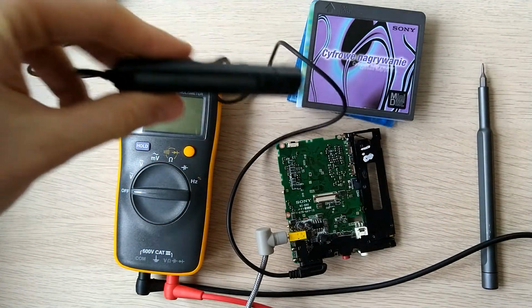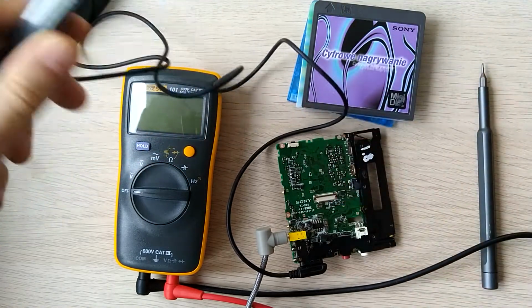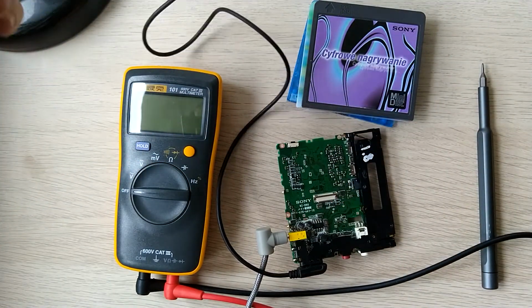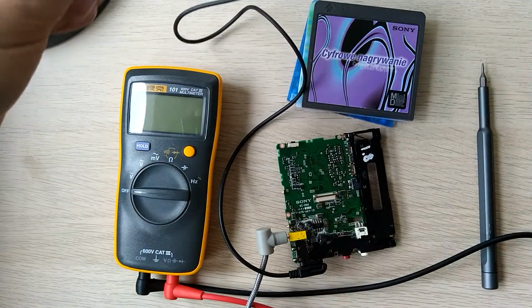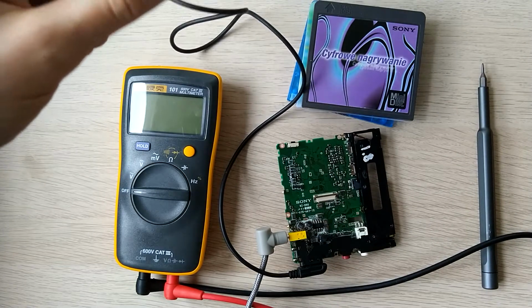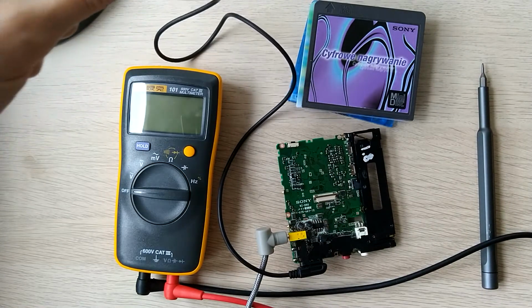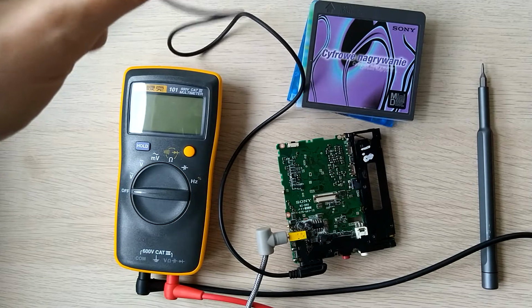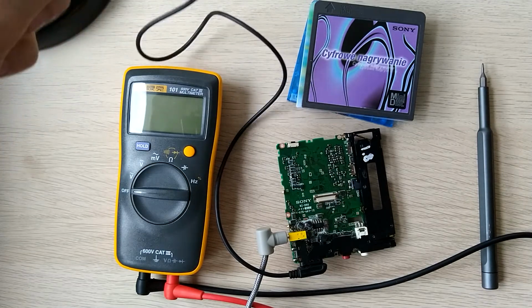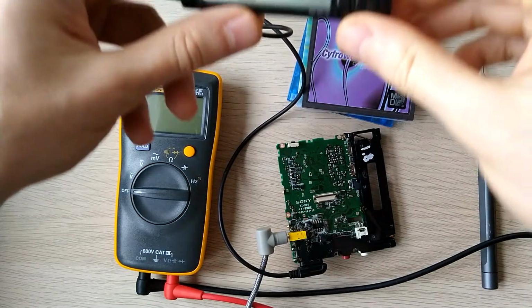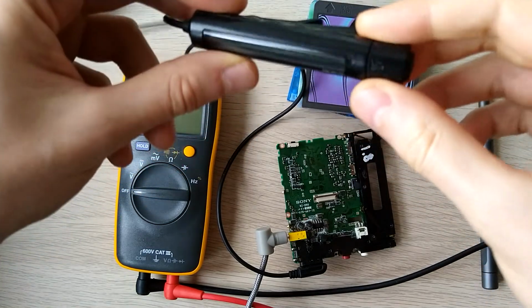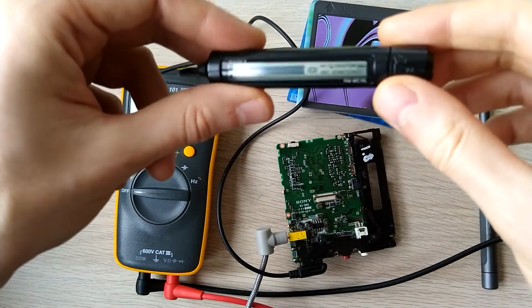The reason why we have to do this is because unfortunately some of the test points that we need are on this side of the board, so we need to disassemble it completely. On other devices the test points might be on the opposite side, so you might only need to remove the back cover. Alright, so following the service manual, the first step is to clear the memory.